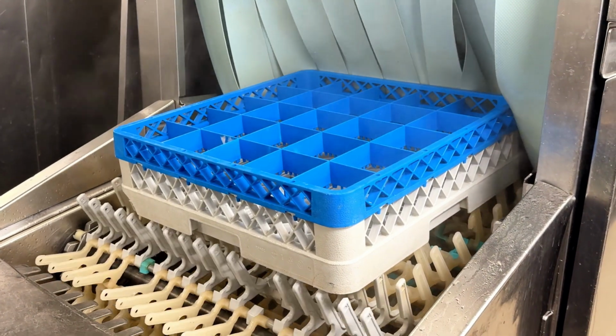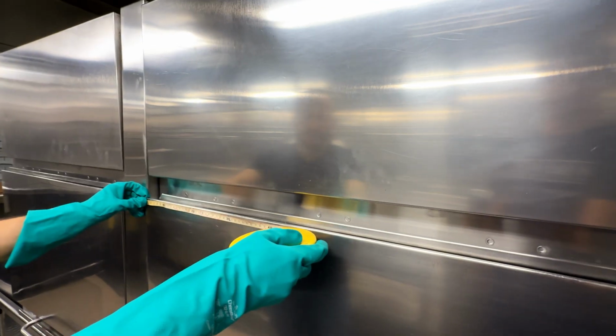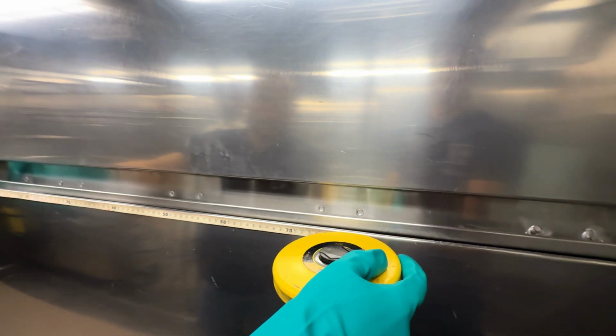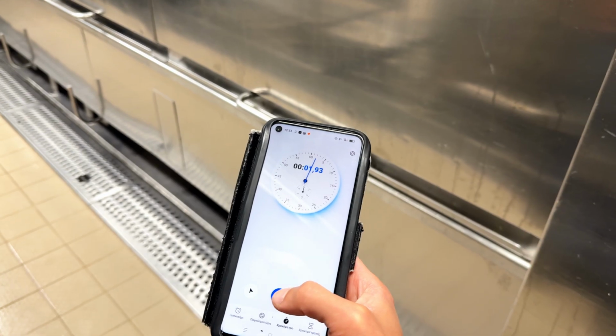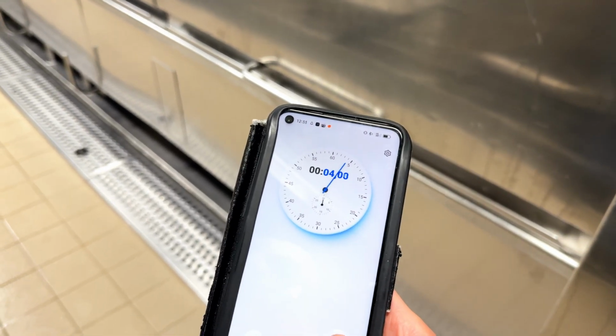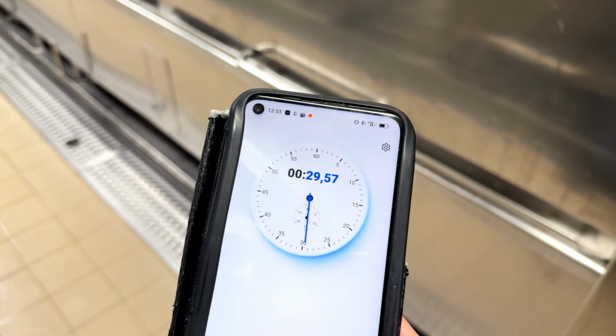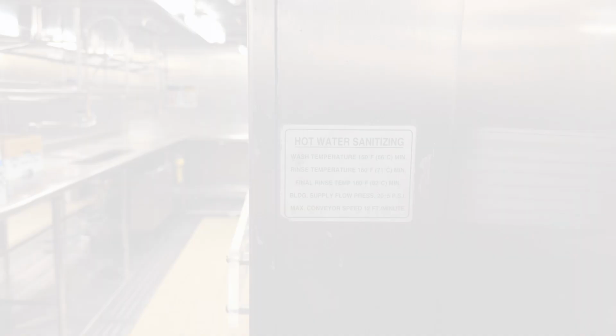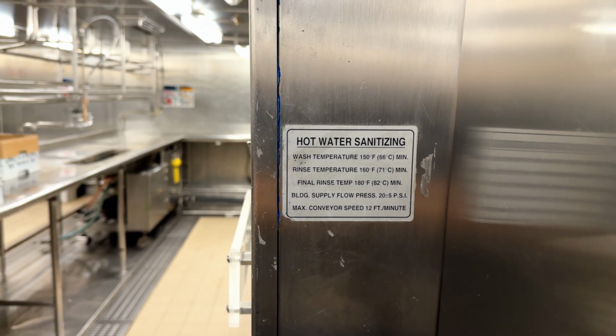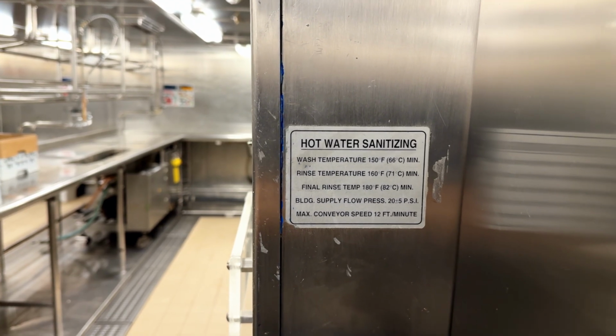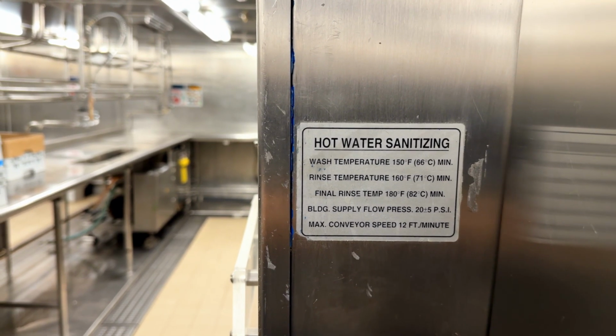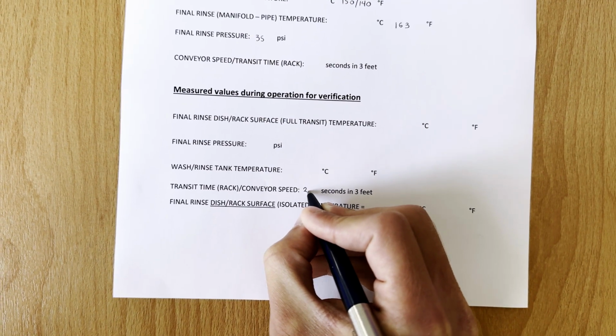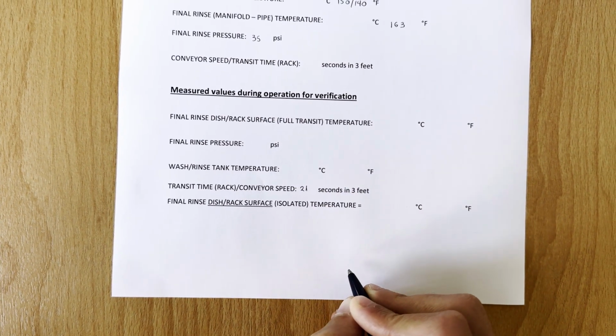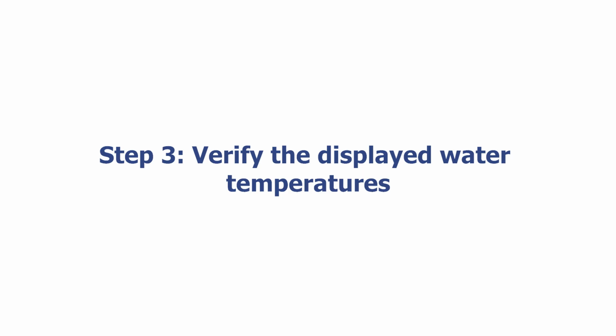Place an empty rack into the machine, then start a timer as the rack is pulled by the conveyor. Remove the rack at the distance used and record the time to determine the conveyor speed. Compare this value to the recorded value from the data plate. The machine is operating properly if the time is equal to or more than the required speed specified on the data plate. Step 3. Verify the displayed water temperatures.